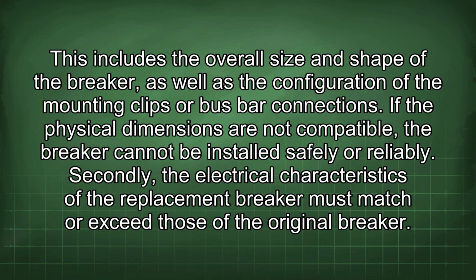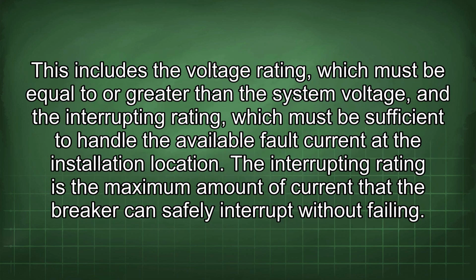Secondly, the electrical characteristics of the replacement breaker must match or exceed those of the original breaker. This includes the voltage rating, which must be equal to or greater than the system voltage, and the interrupting rating, which must be sufficient to handle the available fault current at the installation location. The interrupting rating is the maximum amount of current that the breaker can safely interrupt without failing.